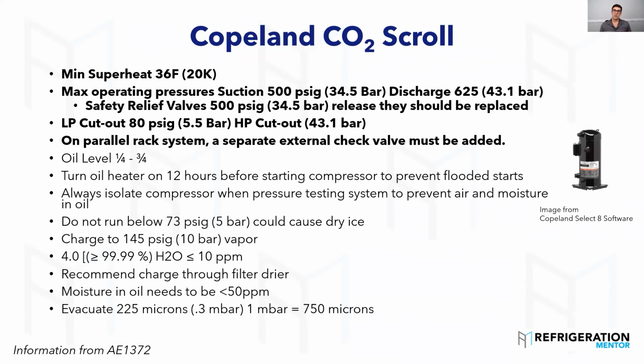Once again, I didn't go through each one step by step like the first one, but minimum superheat 36 F. How do you check this? You take your temperature probe, put it on the suction right close to the suction service valve, and take the pressure right from there. Take your temperature over that converted pressure. You're going to get your compressor superheat, your total superheat, your system superheat. This is what you need to make sure of: you need to keep it above 36 or 20K.